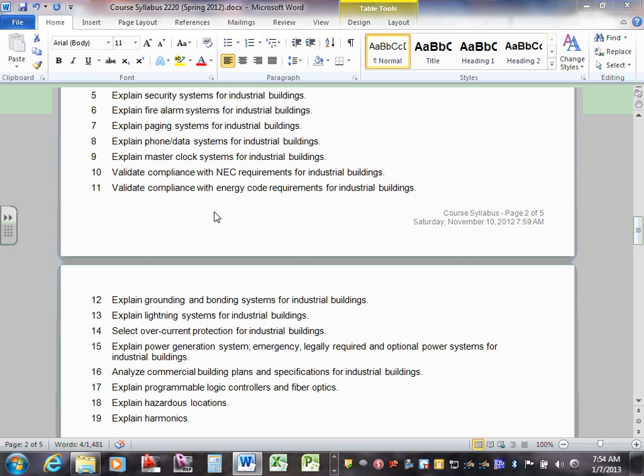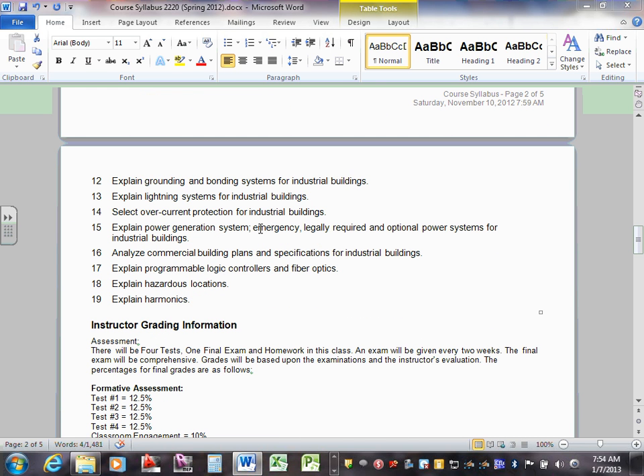NEC requirements all the time. Grounding and bonding - I'm going to spend a lot of time on grounding and bonding. I know some of you guys didn't focus too much on grounding and bonding before. I have a couple of lectures strictly about it: equipment grounding conductor, grounding electrode conductor, main bonding jumper, system bonding jumper, supply side bonding jumper. Everything you need to know about grounding and bonding a 4,000 amp, 480/277 system is going to be in this class.